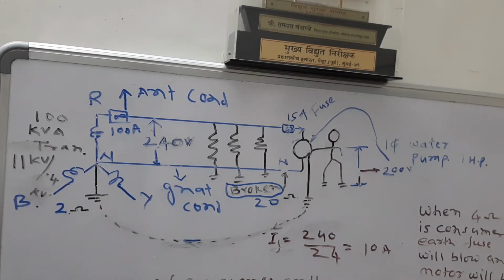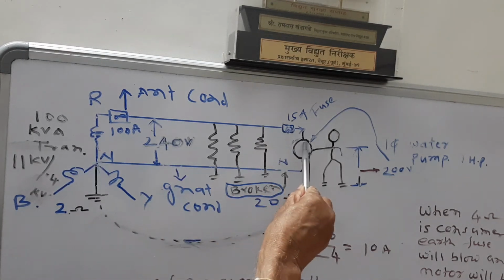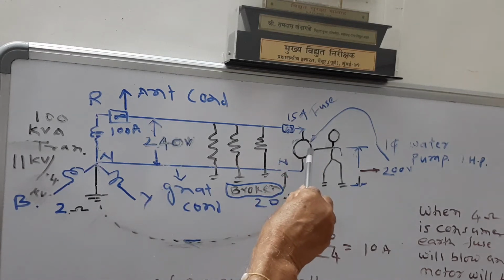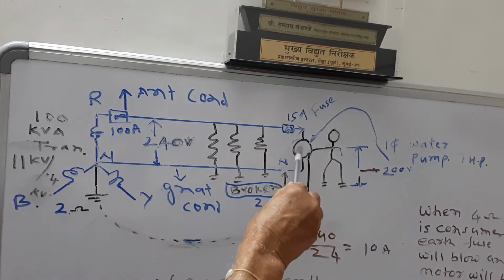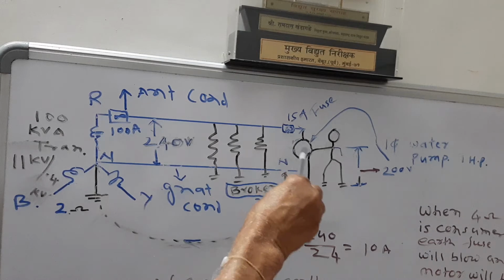whenever we consider safety provisions, we have to consider the last situation, a situation where this neutral is broken. And in your dilapidated network, the neutral breaks here, here, here, here, here, here, and even in the premises of the consumer. And many times neutral is not available to the consumer, even though the supply is supposed to give an effective earth to the consumer at the point of supply as per regulation. However, it never works as per my experience up till now.